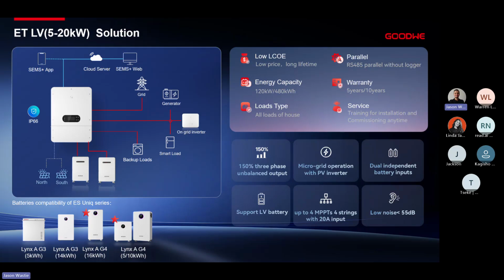On the inverters, we have a built-in DC capacitor bank, and that DC capacitor bank is what allows us to hold these heavy overloads. So we can handle up to, like I mentioned, 40 kilowatts in a 20 kilowatt unit, or 20 kilowatts in a 10 kilowatt single phase unit, up to double the inverter capacity for 10 seconds. The ETLV also handles double PV input oversizing, meaning that we can oversize up to 40 kilowatts of PV on a 20 kilowatt unit and use all of that power.